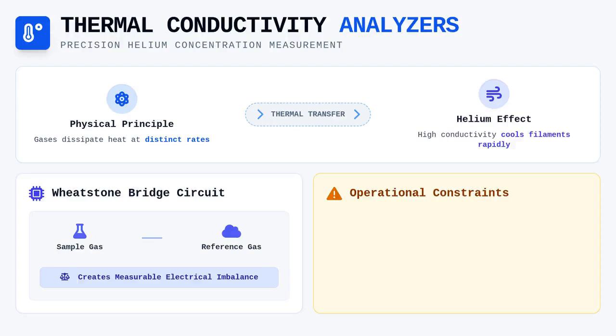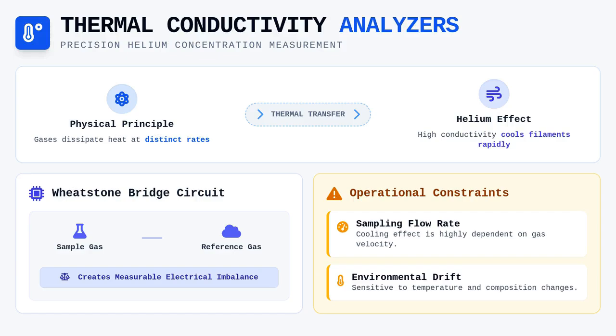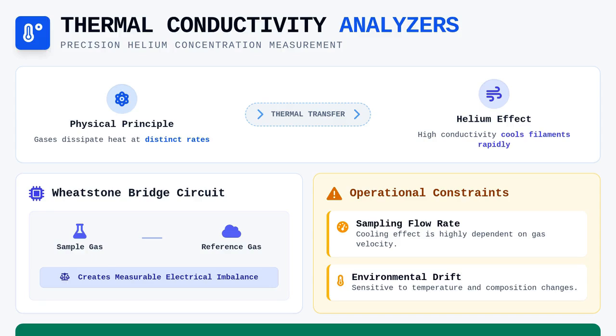When designing these systems, technologists must account for the specific sampling flow rate, as the cooling effect is highly dependent on the velocity of the gas passing over the sensor. You should keep in mind that these sensors are sensitive to gas temperature and composition changes, making them susceptible to drift if the environment is not stable. During your daily routine, you should check the linearity of the thermal conductivity signal across the expected clinical range to verify that the bridge output accurately reflects known standards, particularly when testing lung volumes.